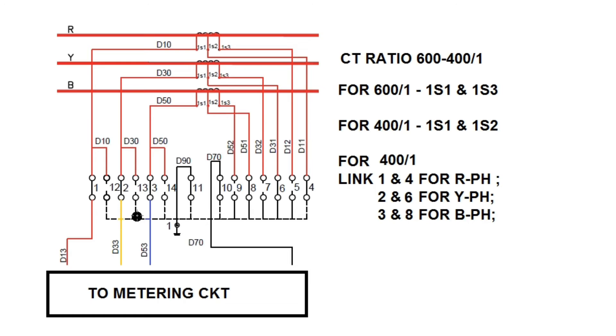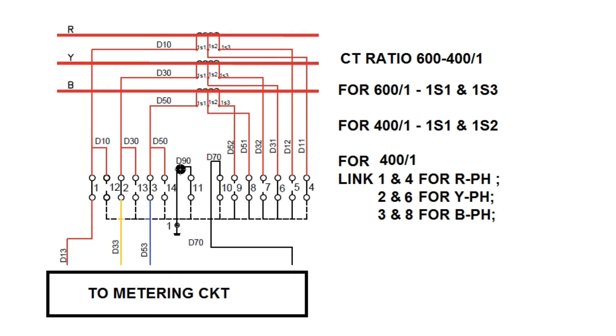On the other side, D13 (red phase) is taken to the metering panel, D33 (yellow phase) is taken to metering for yellow phase, and D53 is taken to metering for blue phase. After the metering circuit, CT shorting is done for the other terminal, neutral is taken out, and D70 is taken back to TB number 10. TB number 11 is connected to earth for earthing purpose.